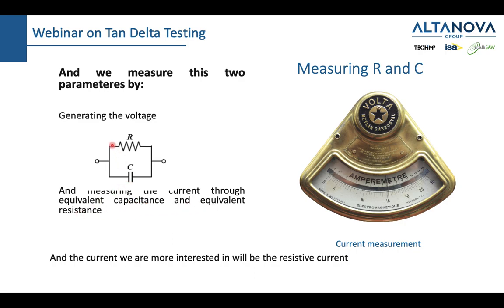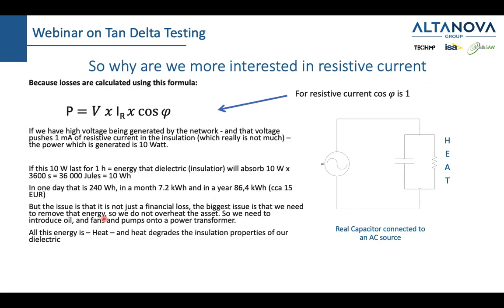We actually cannot measure directly this current and this current. We measure this total current, with an ammeter, of course not like this one, something better, but we do measure the phase shift between the voltage which caused this current and the current which was caused by that voltage. So, of course, we will be more interested in the resistive current. Why? Well, because the resistive current is in phase with voltage, and the resistive current, if we look at this formula, has cosinus phi 1, which means that the power which is dissipated on our insulation actually is voltage times current.